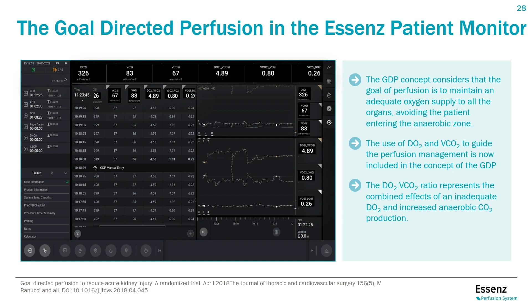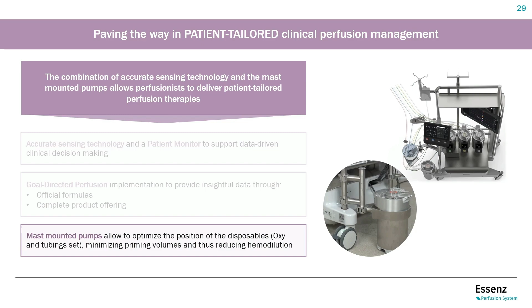In the design of Essenz, we decided to move from the console-based pump concept to 100% mast-mounted pumps in order to give the flexibility to position the pumps according to customer needs and to optimize the position of the disposable, the oxygenator and the tubing set, in order to minimize priming volume and thus reduce hemodilution.